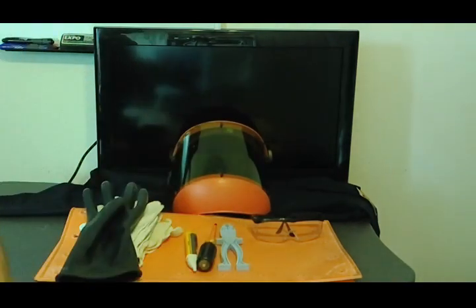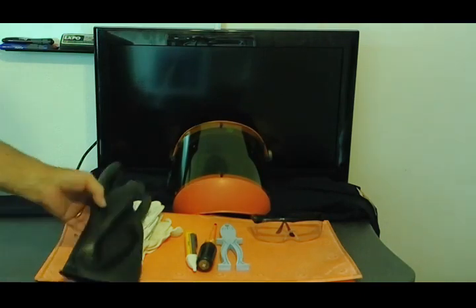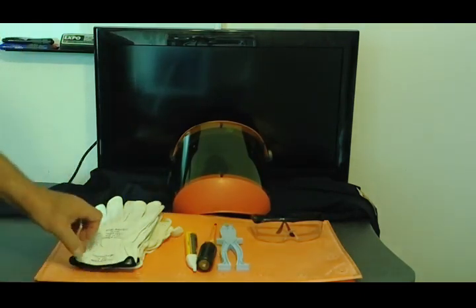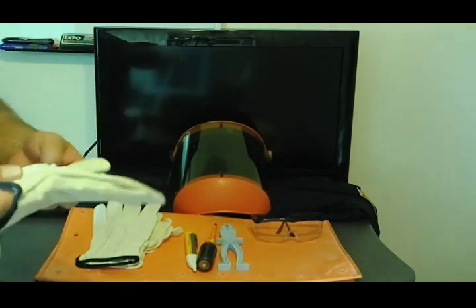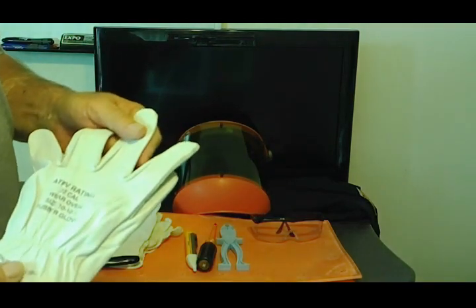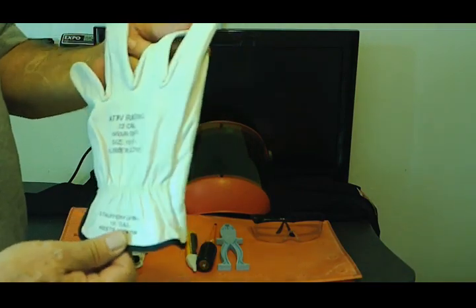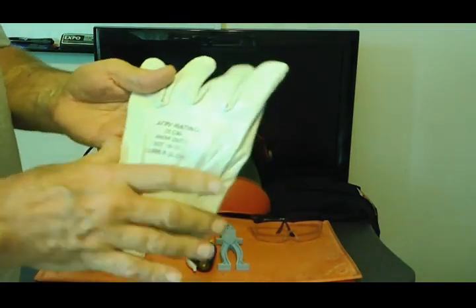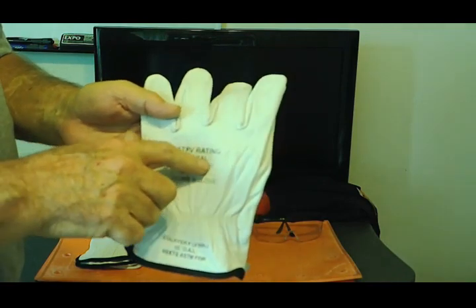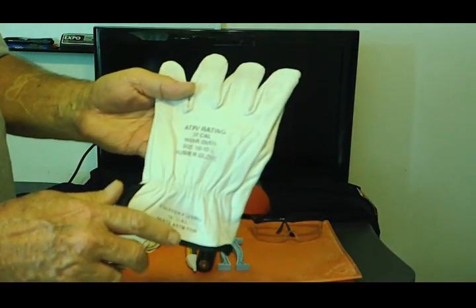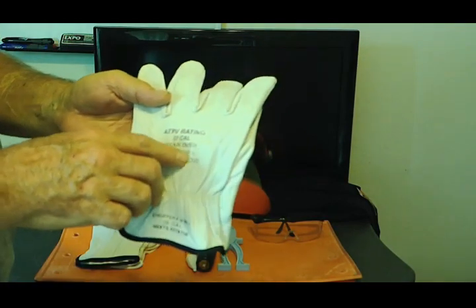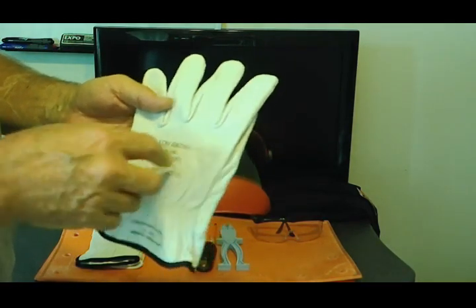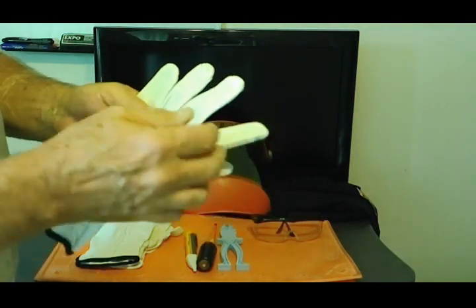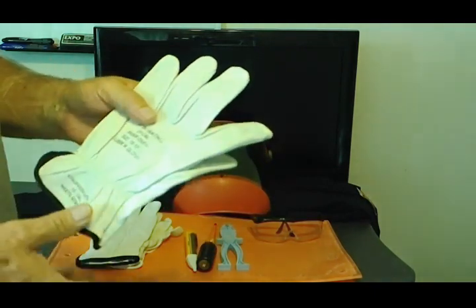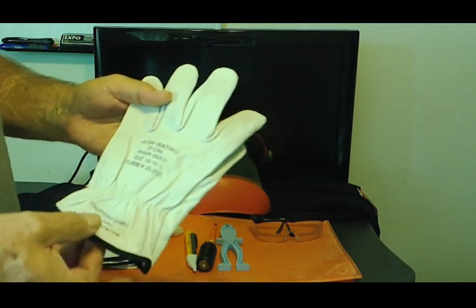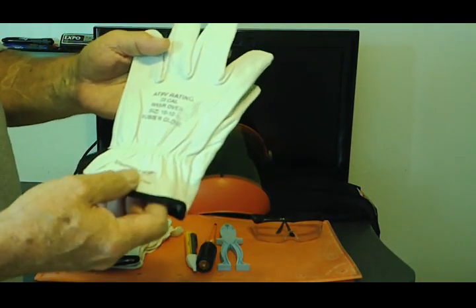Now, gloves themselves are designed to protect you from shock. However, these rubber gloves are not tough. So over the glove, you will wear a leather protector. This leather protector's got a rating of 22 calories, that's for the leather protector all by itself. But it's got to be used with specific sizes of gloves. These fingers on the leather protector are going to be a little bit wider to allow the rubber to fit in. So it is a specialized glove, also made to specific ASTM standards.